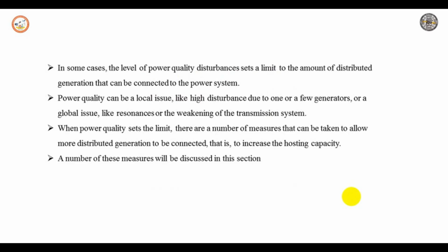The level of power quality disturbance will set a limit to the amount of distributed generation that can be connected to the power system. The power quality can be a local issue, like high disturbance due to one or a few generators, or a global issue like resonance or the weakening of the transmission grid.